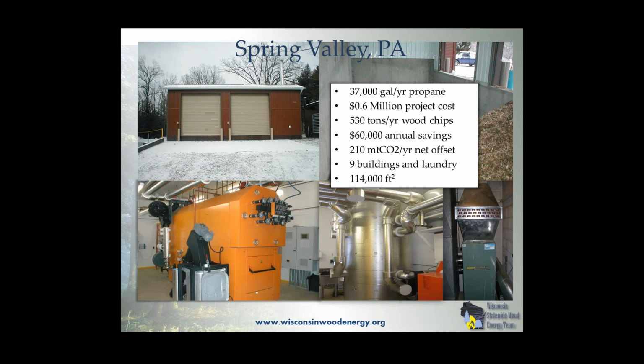This, again, is a Bruderhof community in south central Pennsylvania. They installed this themselves, so the $600,000 price tag might be a little misleading, but they installed all the underground pipe. One of the lessons they learned here was that closed cell foam insulation around pipe is not all created equal. When they say closed cell foam for buried insulated PEX pipe, you need to be sure that it's not closed cell foam wrapped in layers. It's got to be injected into the system so that it adheres both to the central pipe, the carrier pipe, and the outer coating and protection pipe.